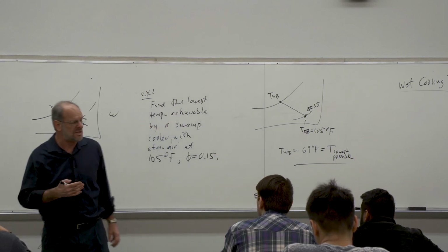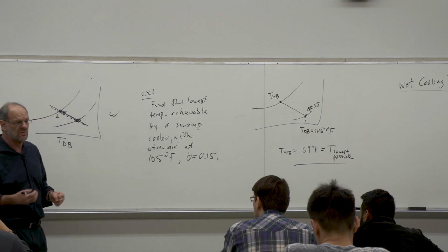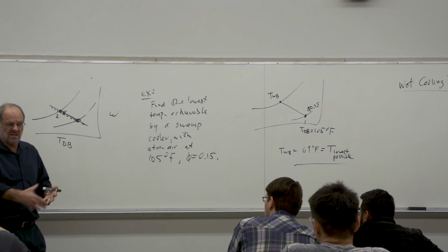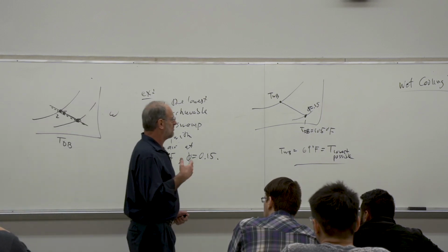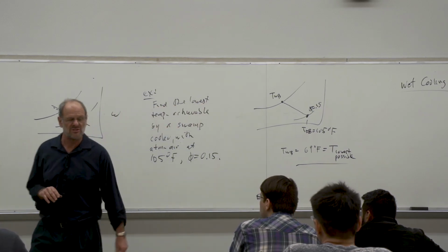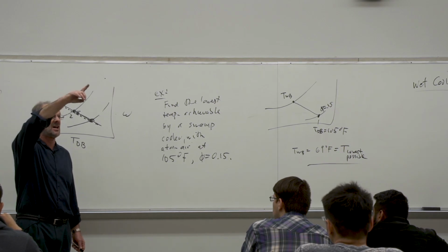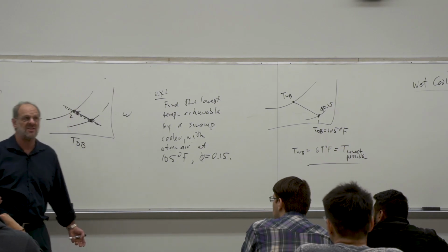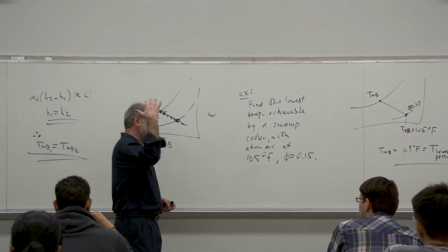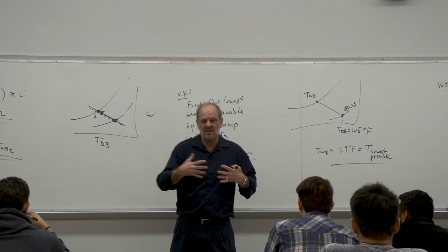But Cal Poly generates millions of gallons of very cold water using a vapor compression refrigeration system. And that cold water is then circulated all over the campus in underground insulated pipes, which are providing the cooling for each and every room that you've ever been in here on campus. There are some exceptions. But nonetheless, it's not like there's a refrigeration cycle inside the ceiling here where all these vents are, right? What's in there are cooling water coils. That cool water is generated by a system up on top of the hill, and the heat that's rejected is rejected into the environment via cooling towers.